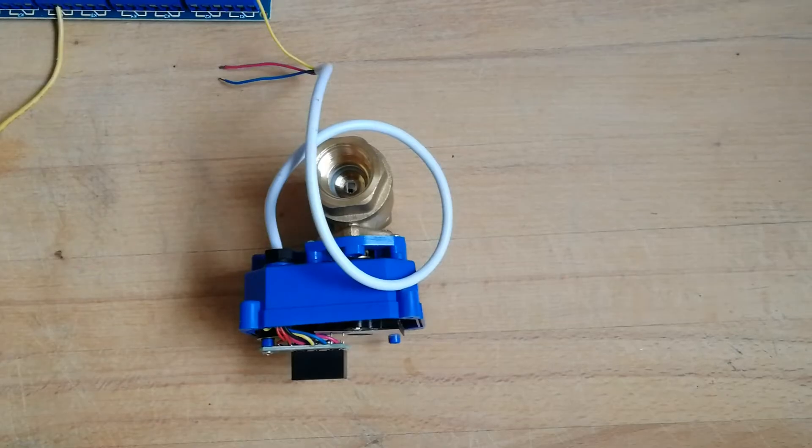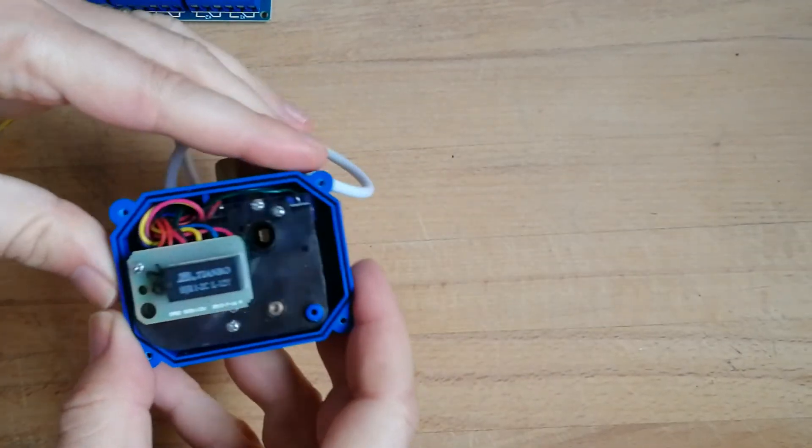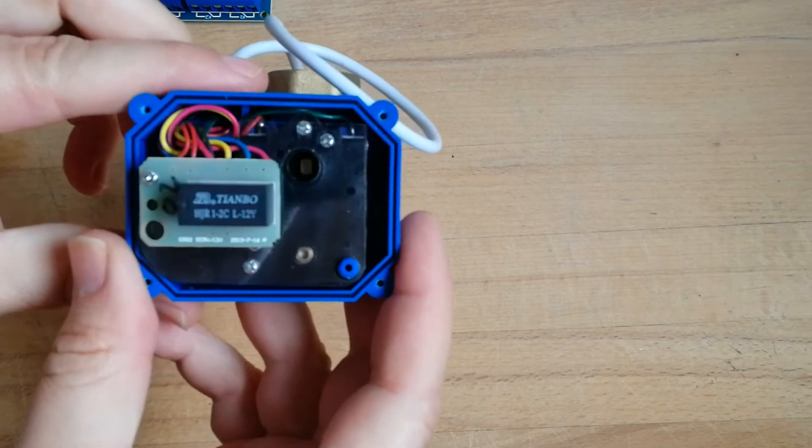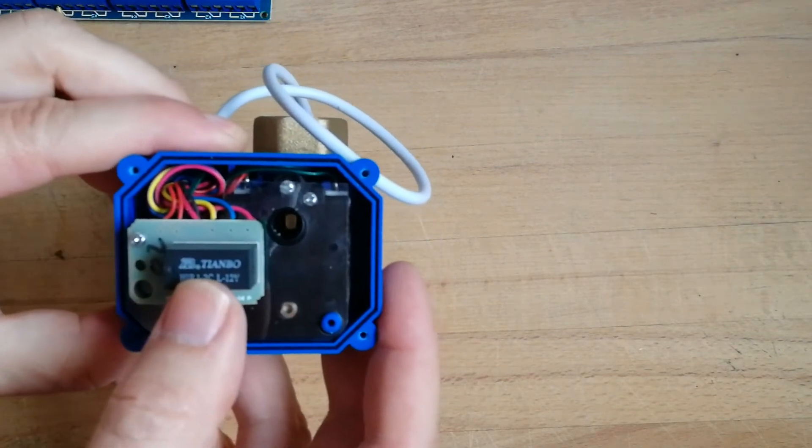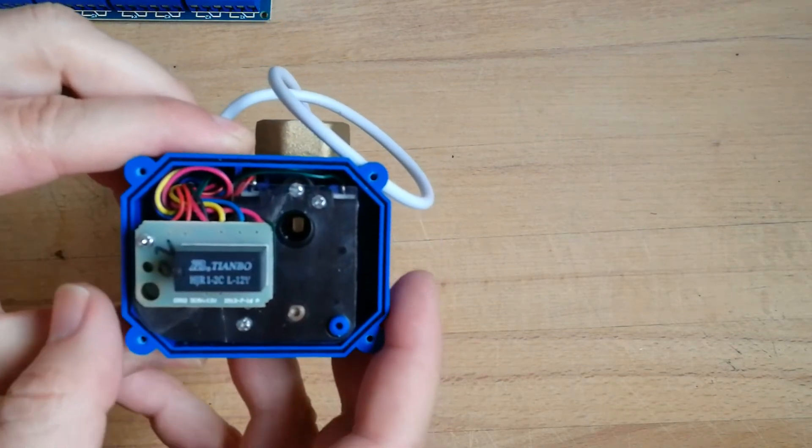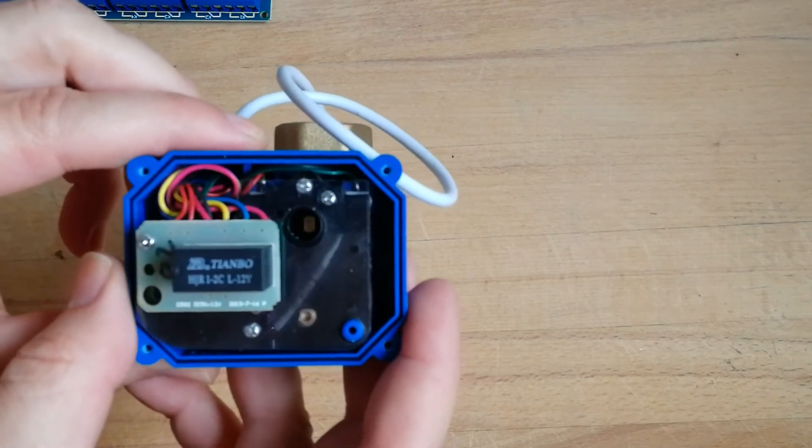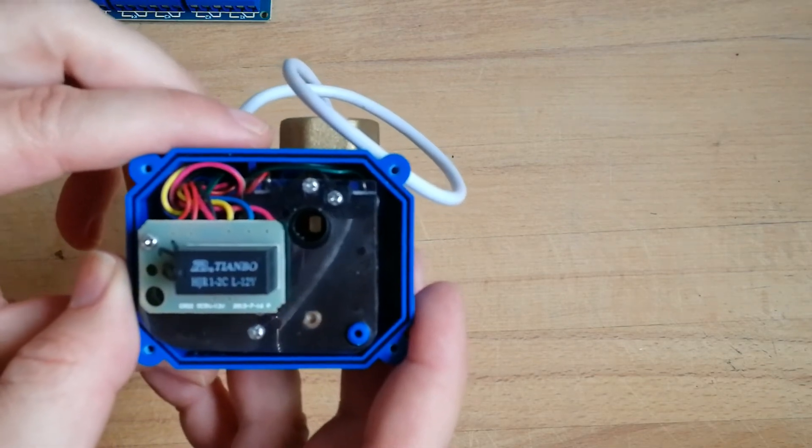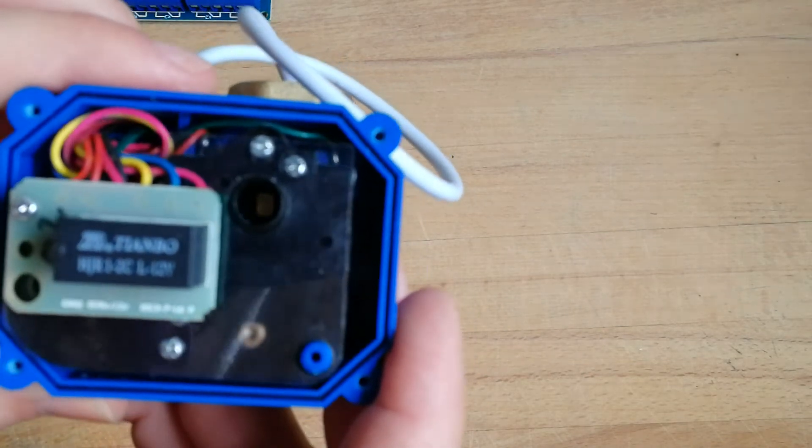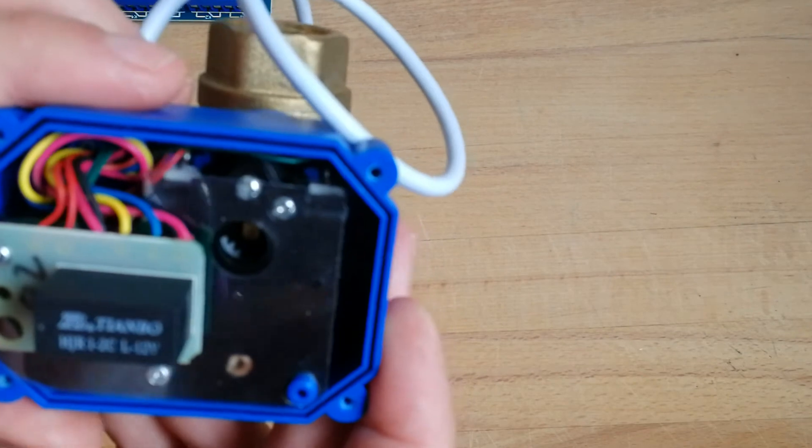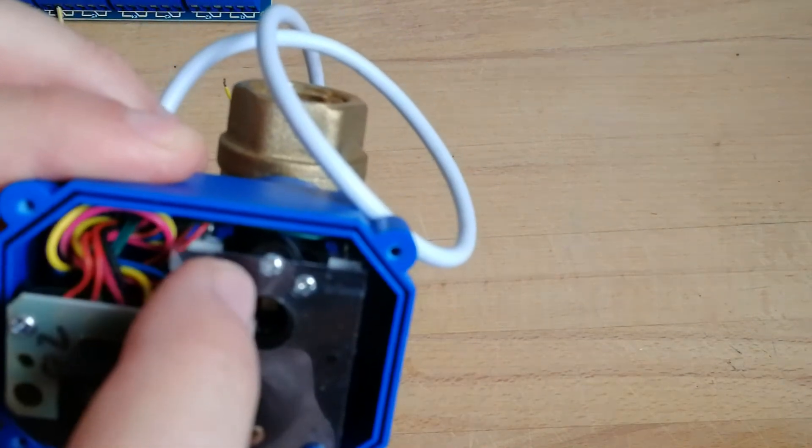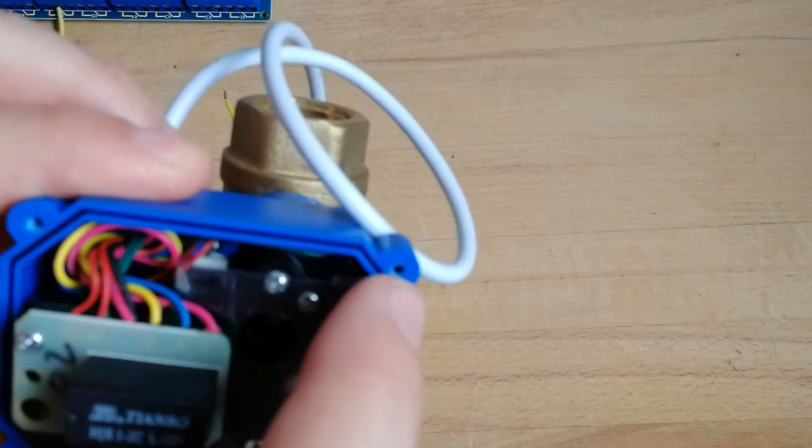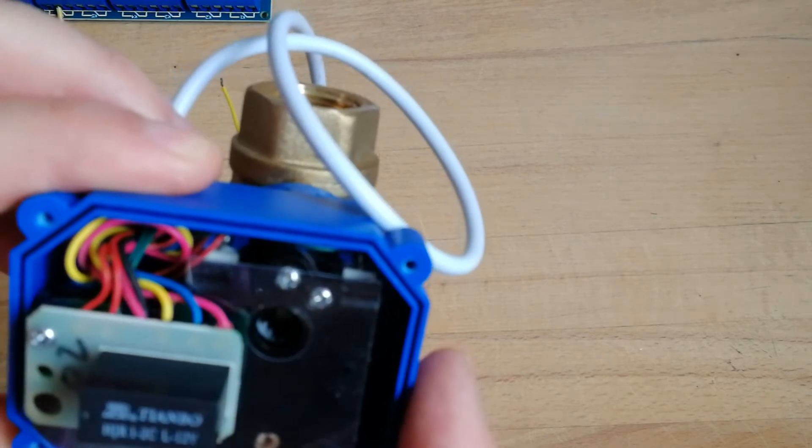So now I opened the valve to see what is inside, and this is what I found. There is a relay, it's a dual switch relay that will invert the polarity for the motor. Then we have the wires that go to the motor, and you can see if you see these two white spots, one here and the other here, these are the end switches.